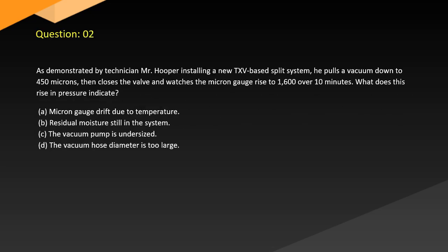Question 2. Demonstrated by technician Mr. Hooper installing a new TXV-based split system. He pulls a vacuum down to 450 microns, then closes the valve and watches the micron gauge rise to 1600 over 10 minutes. What does this rise in pressure indicate?